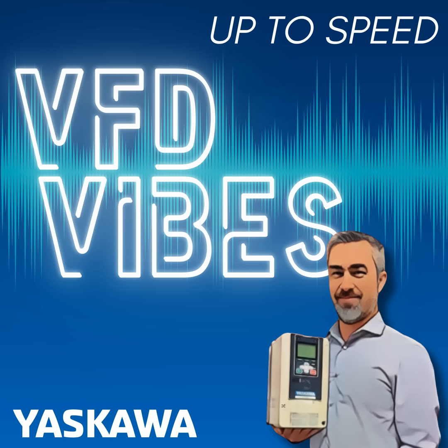Some customers, unable to determine their fault current, specify equipment with 100,000 amps, like we talked about before, figuring there's no way that available is going to surpass that. So that's fairly safe. I won't say it's 100% safe, but it's fairly safe. Or they can also add line impedance, such as a reactor.